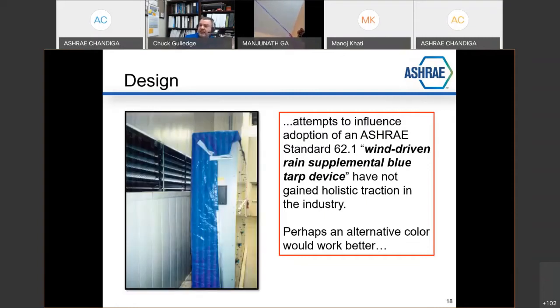Take a look at this. This is electric gear, main power gear, and somebody had to put a blue tarp on it because it was located too close to an outside air intake, a louver, a scenario that was not designed to protect against wind-driven rain. So the face velocity through here was way too high. And when it rained, and they were sucking air in for the systems, it was just blowing water into the main electrical gear. How do we create that scenario? That's just crazy.